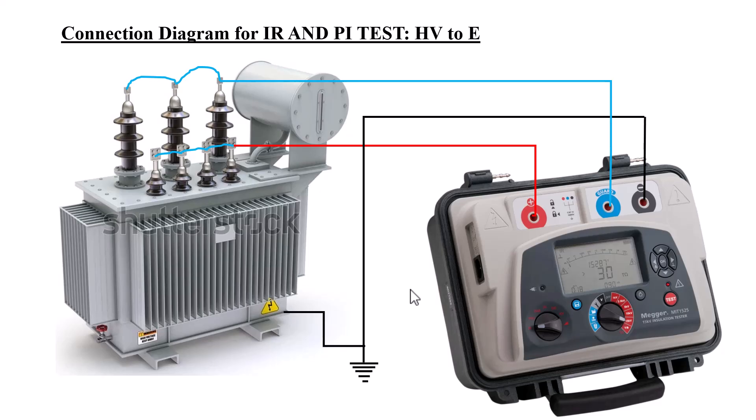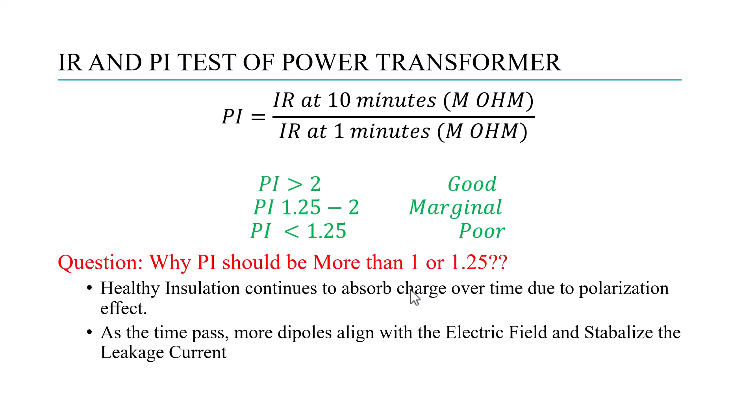Now I will discuss the Polarization Index (PI). The test connection remains the same. The polarization index is the ratio of the IR at 10 minutes divided by the IR at 1 minute. A PI greater than 2 is very good. A PI between 1.25 and 2 is marginal or acceptable. A PI less than 1.25 is very poor, indicating contamination of the insulation — such as moisture — which is not good. The question is: why should PI be greater than 1.25, and why is a higher value recommended?